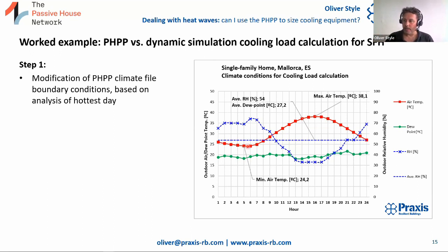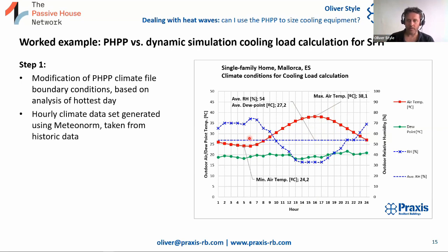So you can see here this example. Here the red line is the air temperature on the hottest day for this location, in this case in Mallorca, reaching 38 degrees. We have the relative humidity here on the blue dotted line with the crosses, and then we have the dew point here on the green line. We've got a minimum temperature of 24 degrees. That's hot. It's not getting cool in the night at all. You're not going to be able to do much with natural night ventilation, no matter how much inertia you put into the building. Really pretty high peak temperatures, 38 degrees centigrade. So this is the evolution, we're looking at a photo of a day here. Of course the average temperature is going to be much lower, and that's what the PHPP is going to be looking at. But we want to look at the peak.